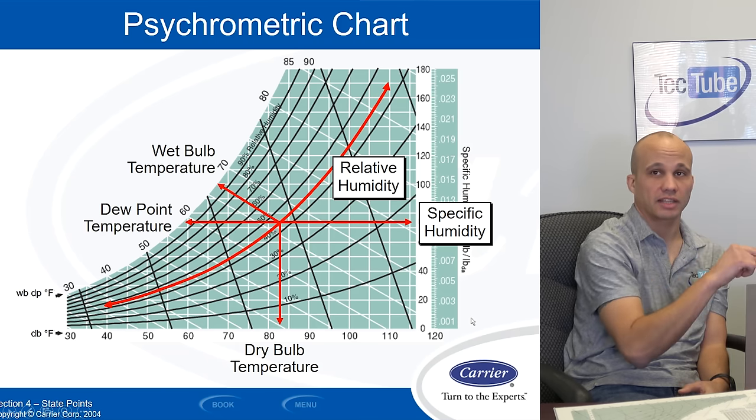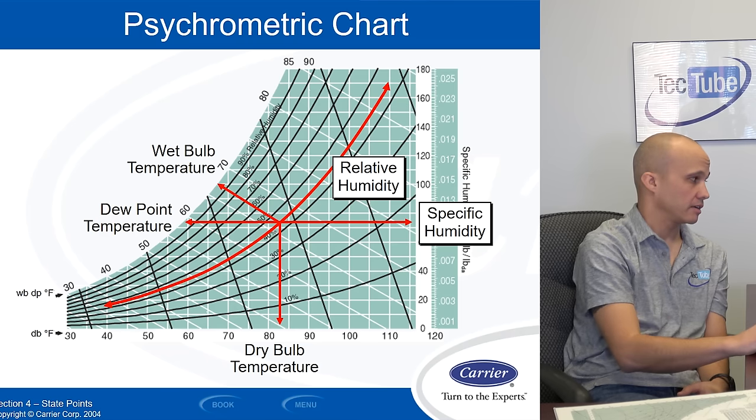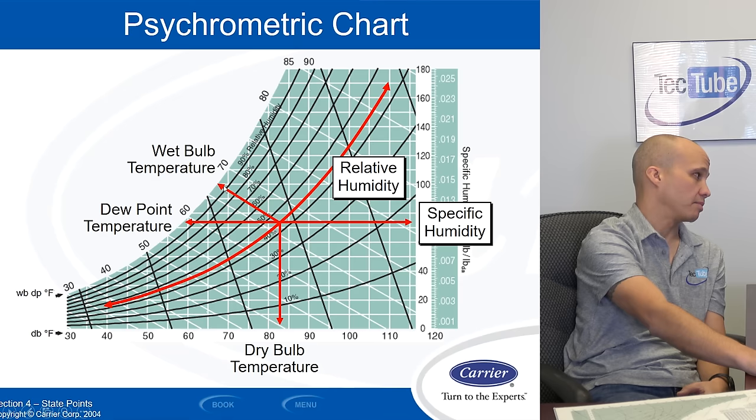So I can read any one of those five variables. If I know two of them, I can plot the point and get the other three from there. Because getting specific humidity is really hard to measure in the field. So I'm going to have to read probably wet bulb and dry bulb in the field and calculate the others from the chart.